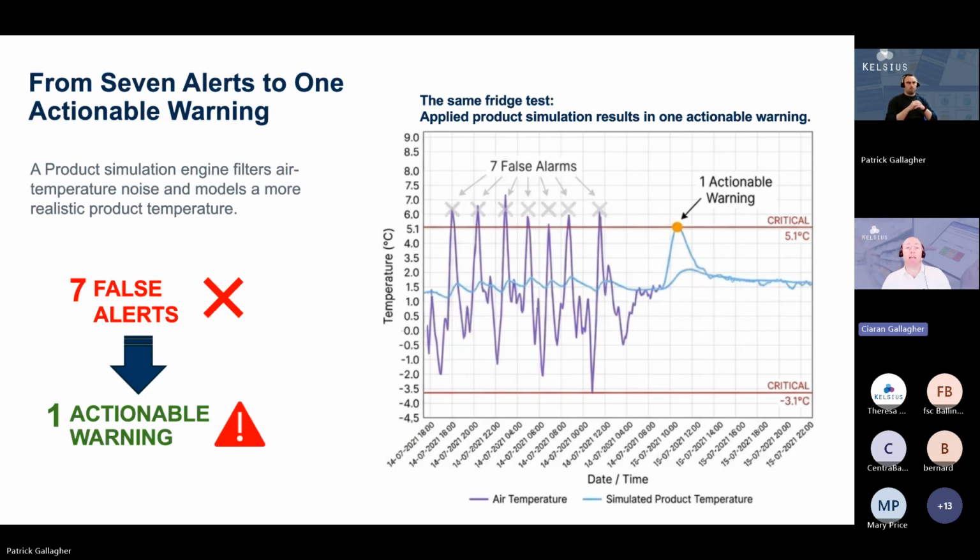So when we look at the performance and the actual data of a given unit, and we compare the data of both the product and the air, back when we started researching this, we conducted studies. We had sensors that applied our bespoke algorithm, placed side by side alongside a sensor with an external probe going into a glycol vial, and a sensor going into an actual product.